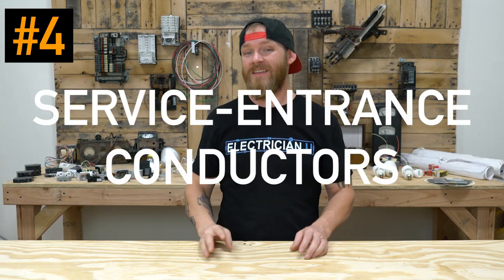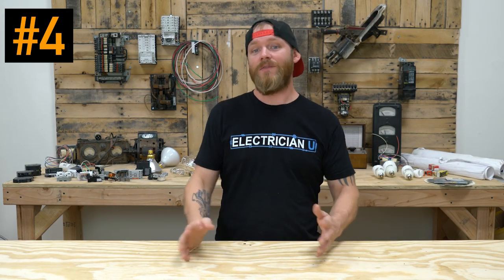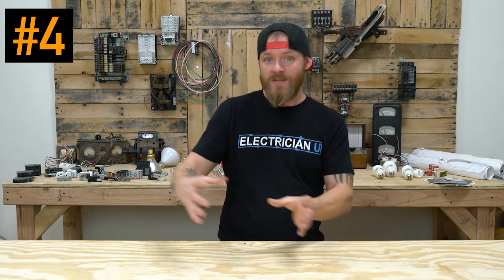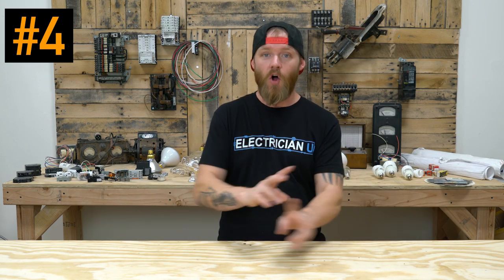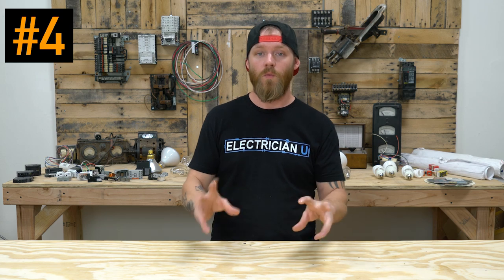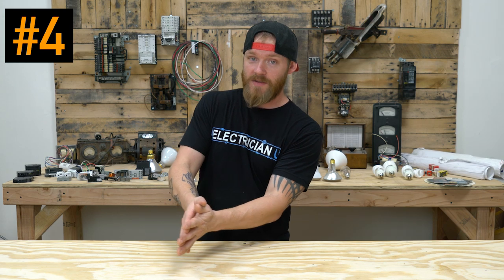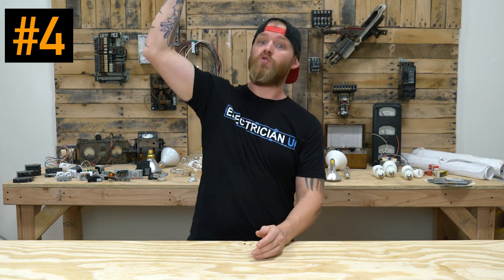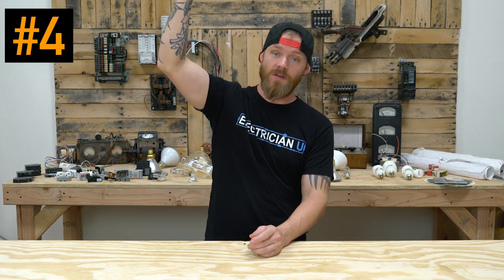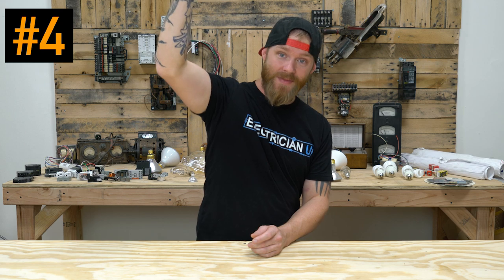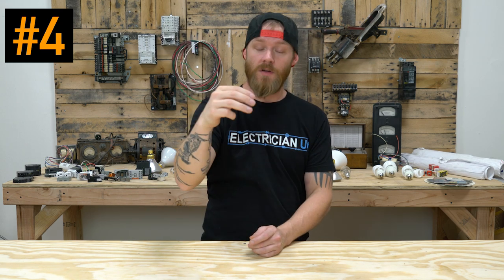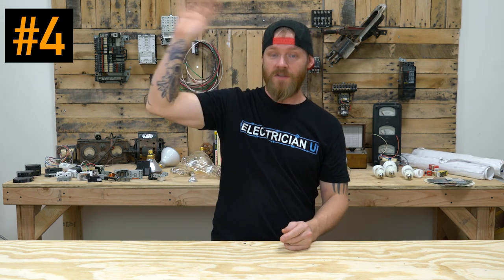Number four, service entrance conductors. Now a lot of people have a hard time with feeders and service entrance conductors, and they kind of call one the same thing and they don't know what the difference is. Service entrance conductors are actually talking about outside at the service, from the service drop or the service point. The point at which the utility hooks up to the service, the wires that hook up at that point and come down into the service and terminate at the first disconnecting means, meaning your main breaker at your service. Those wires are called the service entrance wires.